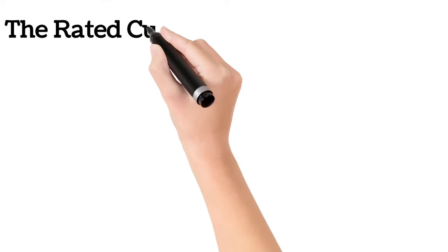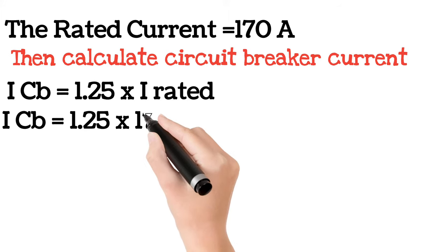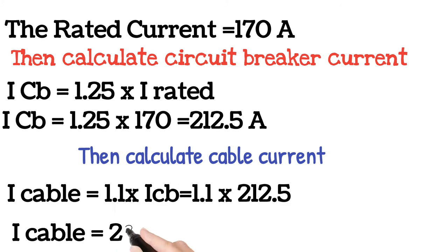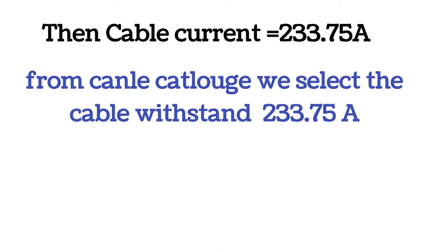Now rated current equals 170 ampere. Then calculate the circuit breaker current, then calculate cable current. From the cable catalogue, we select the cable that can withstand 233.75 ampere.